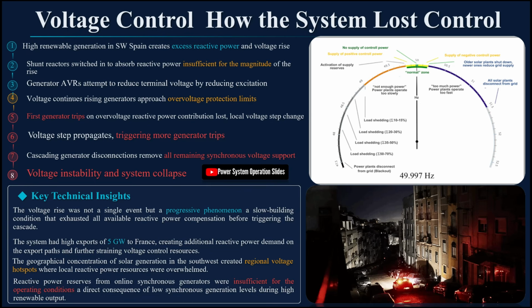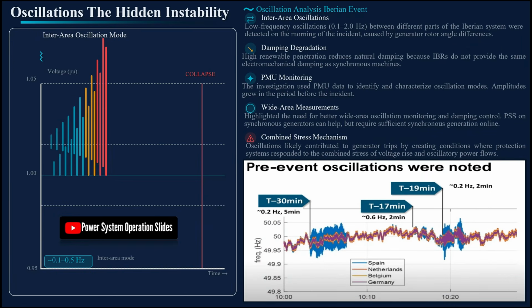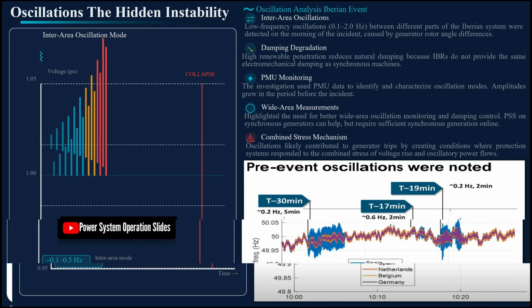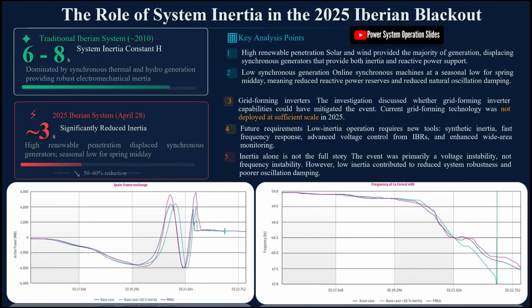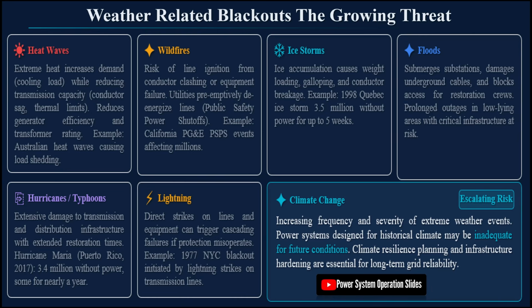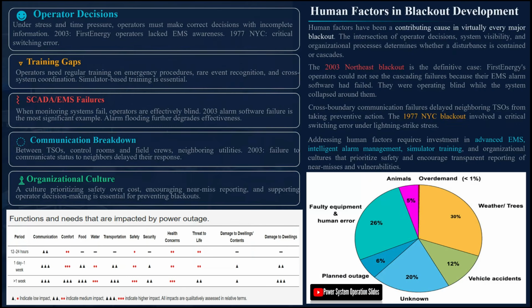The 2025 Iberian blackout serves as a modern case study of how voltage instability and complex oscillations can rapidly collapse a sophisticated, high-renewable grid. The incident was preceded by a rapid, uncontrolled rise in system voltage and a total loss of voltage control in Spain. Technical investigations identified two distinct oscillatory episodes: a 0.63 Hz forced oscillation and a subsequent 0.2 Hz inter-area oscillation. These oscillations were compounded by the fact that renewable energy sources were operating in fixed power factor mode, meaning they could not provide dynamic reactive power support to counteract the voltage rise.